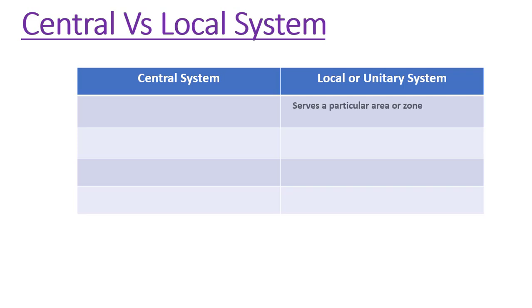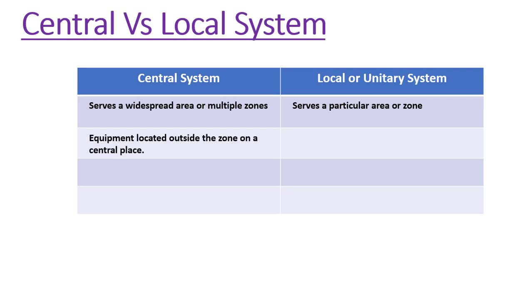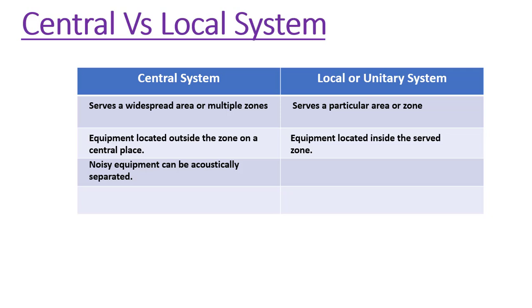In summary, HVAC systems may be organized as local systems with packaged equipment serving a particular area, or as central systems with a collection of plants serving a widespread area or multiple zones. The main benefit of a central system is that all equipment is located outside the zone so maintenance can be easily performed without disturbing occupants. In local systems, the packaged equipment is inside the zones, so maintenance is not easy. Also, in central systems, noisy equipment can be acoustically separated.